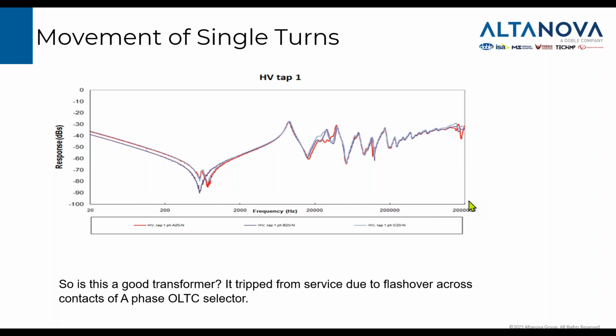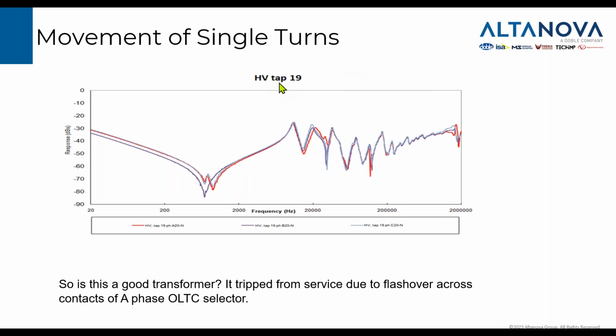And then we started testing. We did the first sweep of the frequency response test, and we saw an almost, let's say, good response. All three match each other with relatively good accuracy, but there are some differences, and especially the red phase is more different than the other two traces. Here, a little bit also here, a little bit here. We said, okay, let's try different tests. This was high voltage tap 1, so we did it at tap 19 without the regulating winding. So we have A phase visible here as well. This was visible here, and again in some other points, again standing out slightly from the two other phases.